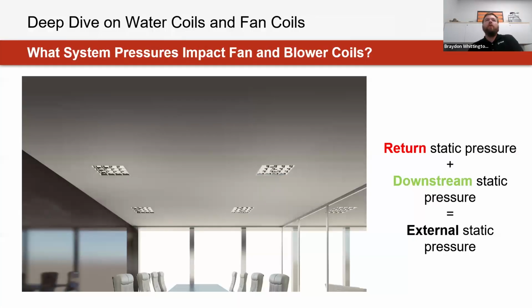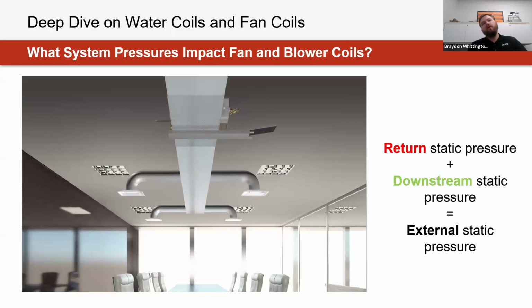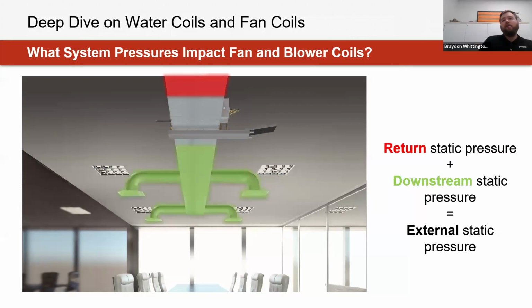And when talking about a system approach, and I think this is going to be really good, especially before we talk about a case study or example here in a little bit, is consideration of system pressures or how they apply when talking about fan and blower coils. And with this equipment, a lot of the time this is taken into account as external static pressure in terms of the total resistance that that fan is trying to compensate for. And how that really ties in is, well, how much additional static are our downstream conditions adding to it, whether it be our duct lengths, bends in this ductwork, or GRD downstream from the product itself. Then also for ducted applications, how much return static are we seeing there as well, whether it be connected to other zones or other spaces, or how long that trunk line is going to be that fan is trying to draw air through too.